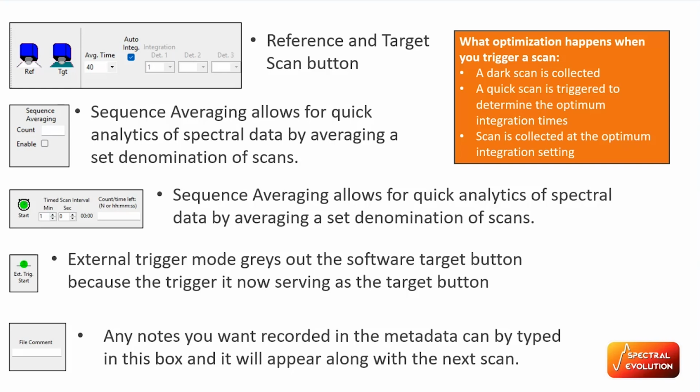data. So I often reference whatever count that you put in here and you hit enable. Say you put 5 and enable. That means on your 5th scan, it will average the last 5 scans together to give you the average 1 through 5. It will still have all of your data broken down, each individual scan, I mean, but it will automatically collect that average scan so you can look at it. So if you're characterizing, say, an outcrop or transect, and you know that you're taking 10 scans at each location, you could put 10 and then have the average quickly calculated for you.